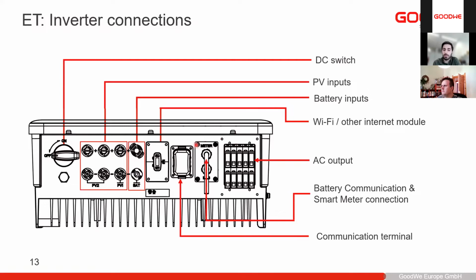Instead, on the right side, you have two different cables coming out. One is for the smart meter, and the lower one is for the BMS to the battery. As you see here, these are already pre-wired. We'll also see it later on. The only thing you need to do is connect them, or if you want to reduce the cable length, you can also shorten the cable.